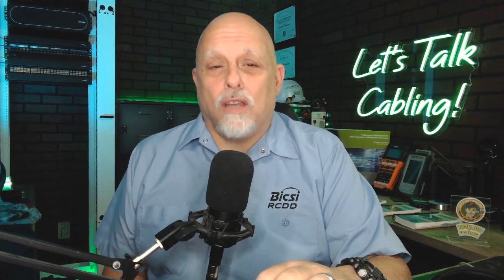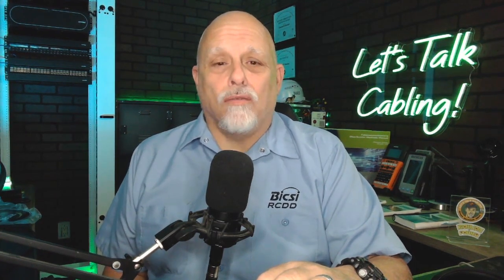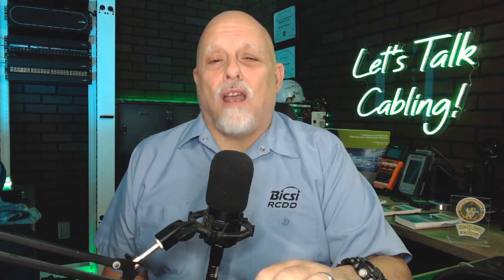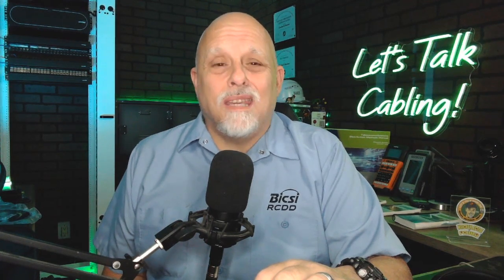Imagine this. Your cables are running through a building, doing their job, transporting ones and zeros from one end of the cable to the other end of the cable. What happens if a fire breaks out? When the cable jacket burns, the conductors start to collapse and the jacket starts to burn off. And the size that was once a tightly packed cable bundle begins to shrink. And this is where intumescent firestop materials come into play. These materials are designed to expand when exposed to heat, filling that space left behind by those shrinking cables.